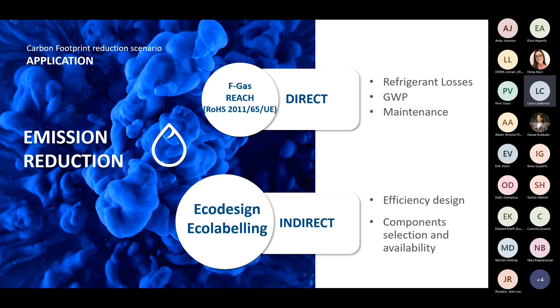The second approach is about eco-design and eco-labeling, which is something to do with the indirect emissions and therefore designing the proper system in order to increase its efficiency. And it's about selection and availability of the proper components. We could no longer use the existing components for approaching this big challenge. Again, these two approaches must be combined together. And the parameter that we always need to keep in mind is the TEWI, total equivalent warming impact, which, through a formula that I will leave for your reference, combines the direct impact of refrigerant losses plus the indirect impact of energy consumption.